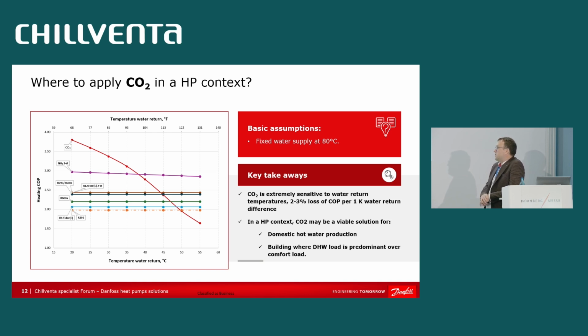And those conditions really rely on the water return temperature on the gas cooler side, which needs to be as low as possible in order to maximize the performance. Otherwise, the performance is quite lower versus other types of refrigerants, such as the subcritical ones, propane, isobutane, or ZD. So like I said, CO2 is extremely sensitive to water return temperature. There is a 2 to 3% loss per 1K water return temperature difference.